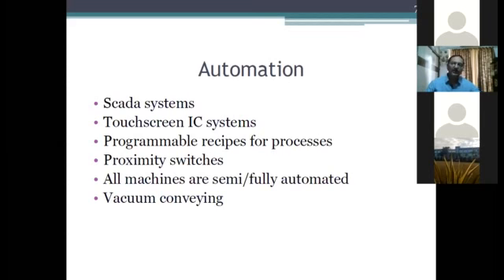Let's say if you are doing rubber stoppering and the rubber stopper machine is having a problem, then the vials will be collected on the conveyor, so the filling machine has to stop, otherwise everything will be jammed. There is a proximity switch on the conveyor so that if the vials collect beyond a certain level, the filling machine will stop. If the filling machine stops, the turntable on which the vials are coming from the sterilizer gets a signal, so the tunnel sterilizer will stop. And when the tunnel sterilizer stops, it gives an indication to the washing machine, so the washing machine stops.